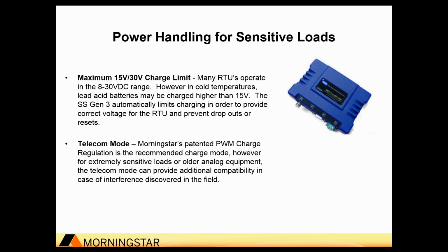Power handling for sensitive loads. We've taken into account a lot of your feedback on how RTUs may have a narrow voltage operating window. And in those cases, we limit battery charge voltage to either 15 in a 12-volt system or 30 in a 24-volt system to prevent damage from the load.